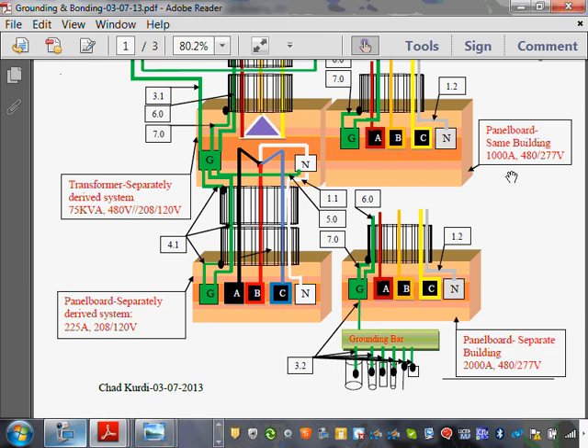So this is a transformer. In 2011, yeah, 2011, absolutely. If your separately derived system is located outdoors, for lightning and so forth. If it's indoors, you bond to, and why would you put it outdoors? The only thing I can think of for putting it outdoors is if you want to feed a separate building. Or cooling, there you go, good point, yeah, if you want to cool it and bring it back. It's in the building, yeah, get exhaust out. That's generators, what we're talking about, like for generators, yeah. But for transformers, you have to drive a ground rod. We'll get into the generator in a second. Any comments, guys, about this?